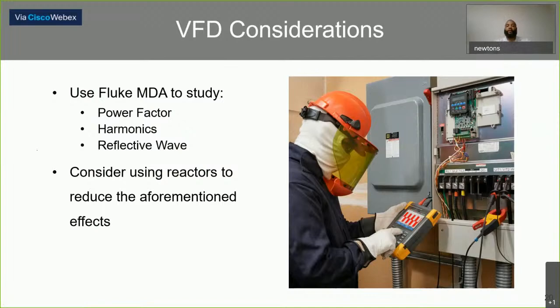So what are some tools that you can use to monitor or view or trend reflective wave, harmonics, or power factor? One that I highly recommend is called the Fluke MDA, or a motor drive analyzer. Essentially, it's a high-end oscilloscope that has some firmware on it that is very friendly for the user that's in the field, whether that's your engineer or your technician, electrician, whoever is qualified to work on this equipment. From there, you can print out some nice reports, get some useful information to, one, monitor the health of your motors or your drives, or in this case, your cables as well.